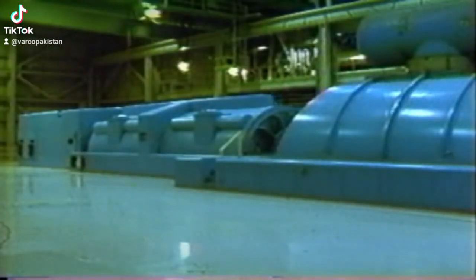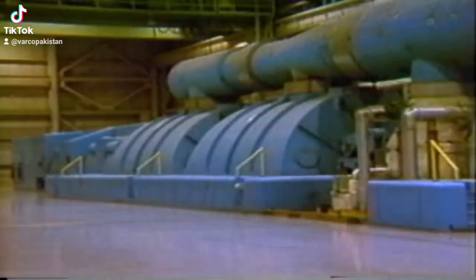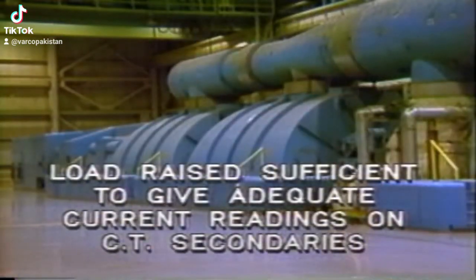Once the generator is paralleled to the bus, load on the turbine generator can be raised sufficient to give adequate current readings on the CT secondaries, and so allow in-service readings to be taken at the CT links.